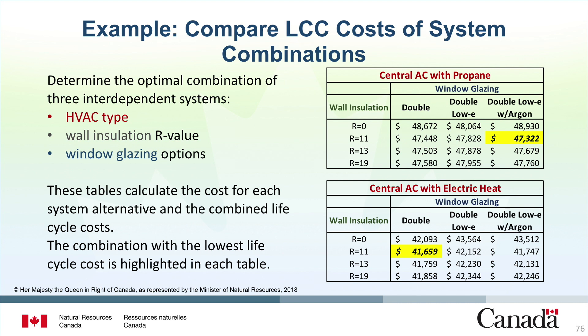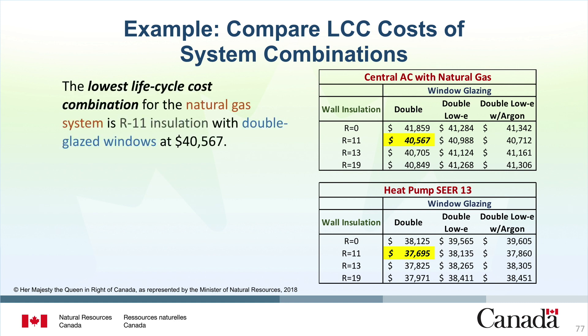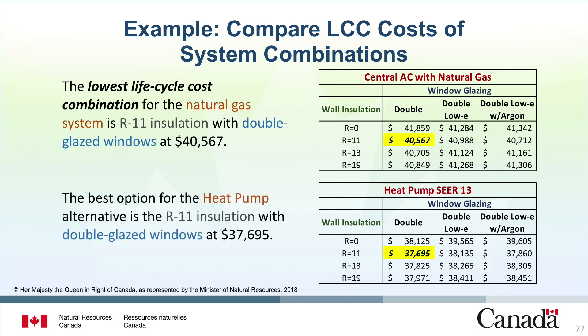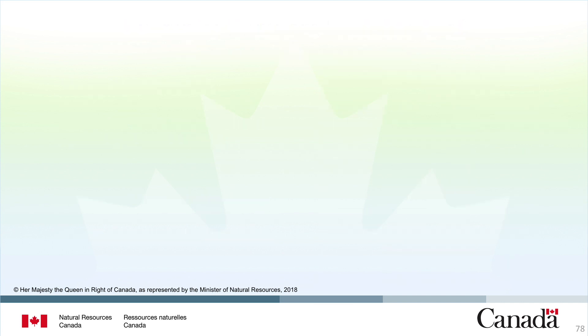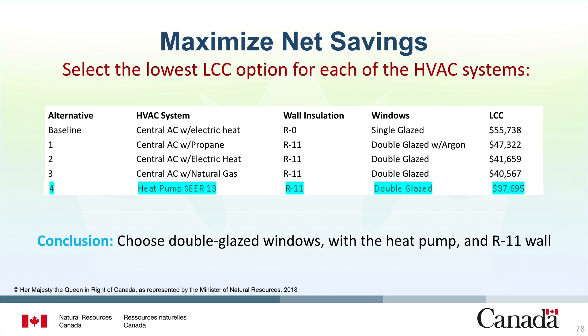For window glazing, we will consider three options: double glazed, double glazed with low-E, and double glazed with low-E and argon gas fill. These tables calculate the cost for each system alternative and the combined lifecycle costs, with the combination with the lowest lifecycle cost highlighted in bold. For the first system — central AC with propane — the best option is R11 wall insulation and double pane windows with argon fill at a cost of $47,322. For central air conditioning with electric heat, the best option is R11 wall insulation with double glazed windows at a cost of $41,659. For the natural gas system, the best option is R11 insulation with double glazed windows at $40,567. The best option for the heat pump alternative is R11 insulation with double glazed windows at $37,695, the lowest of all available options — therefore this is the optimal combination to select.